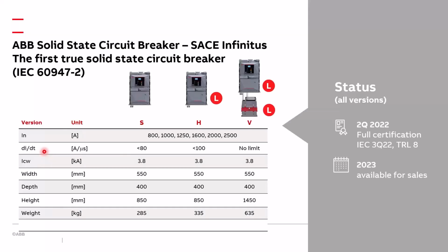Unlike the traditional circuit breaker, where we have a breaking capacity of tens or hundreds of kA, here it is not a matter of the steady state value of the short circuit current, but a matter of derivative. For example, we can have a prospective short circuit current up to 1 million amp, but if the derivative of the current, according to the total time constant of the system, is lower than 80 amp per microsecond, we are able to interrupt a sort of unlimited prospective short circuit current.